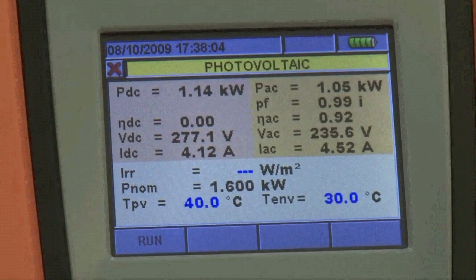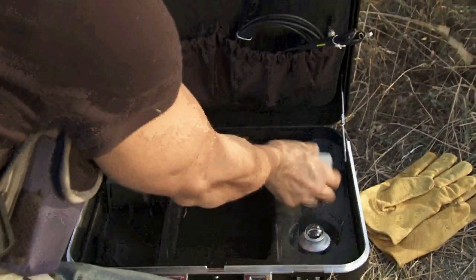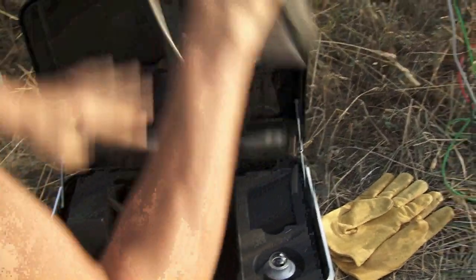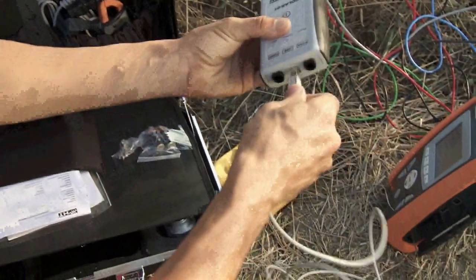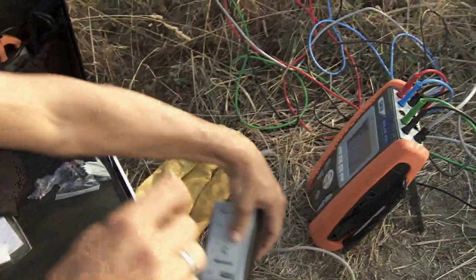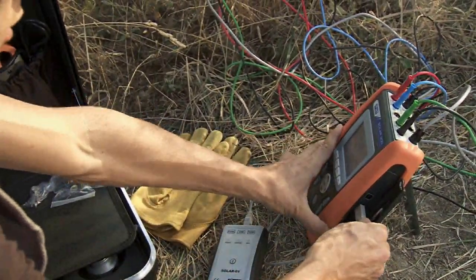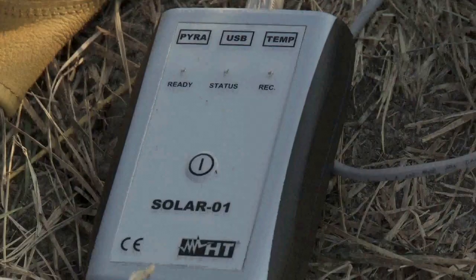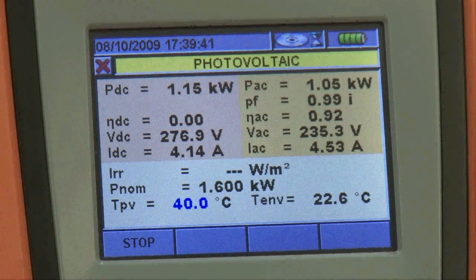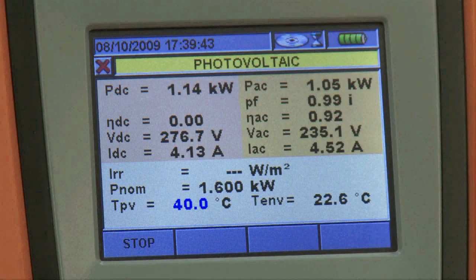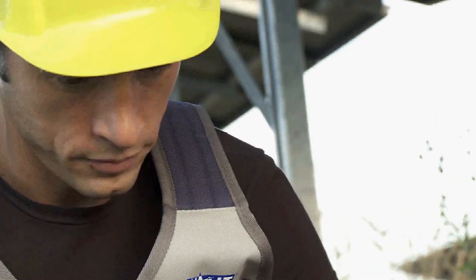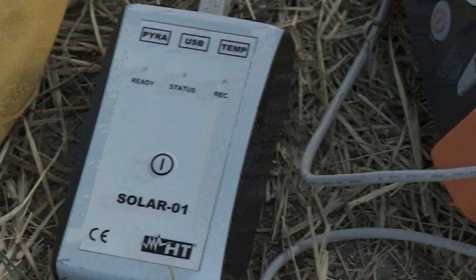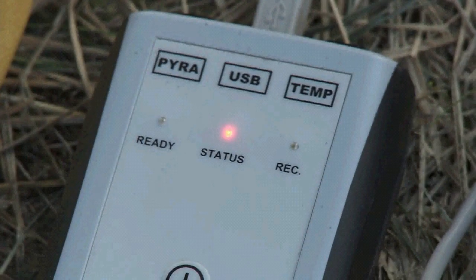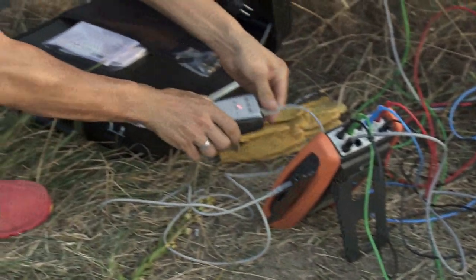The inverter can be positioned in a part of the system which is not attached to the voltaic panels. Therefore, SOLAR300N is fitted with an independent recording unit to record irradiation and temperature of the environment and of the modules. Pressing the F1 key after connecting the two units by means of a USB cable synchronizes the internal clocks of the two units, thus guaranteeing simultaneous reading. While measuring, no connection between the two units is required, whether by cable or by radio. Once synchronization is complete, the two units can be disconnected and the remote unit taken near to the modules to be tested.